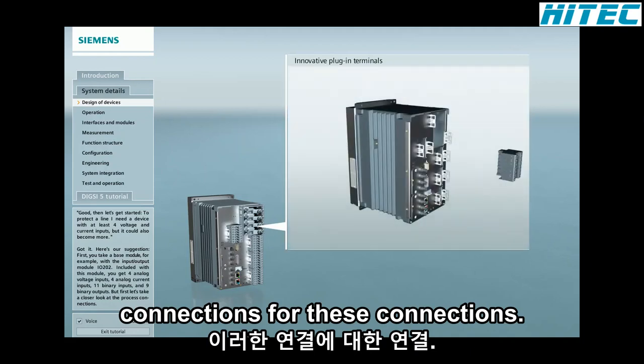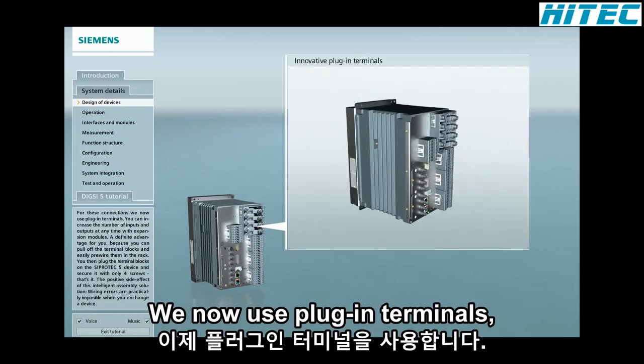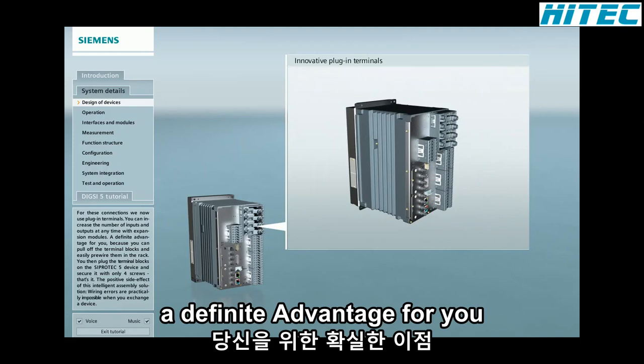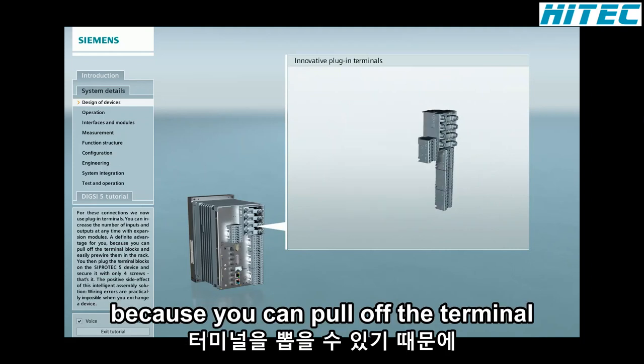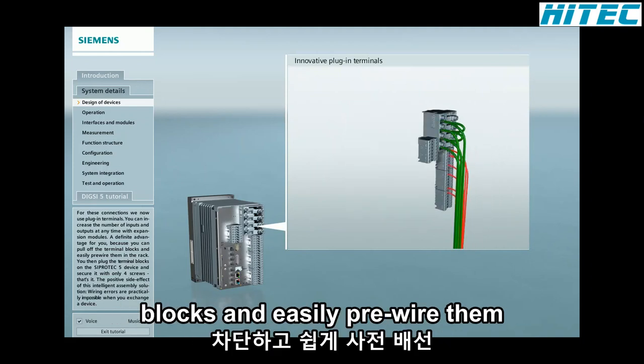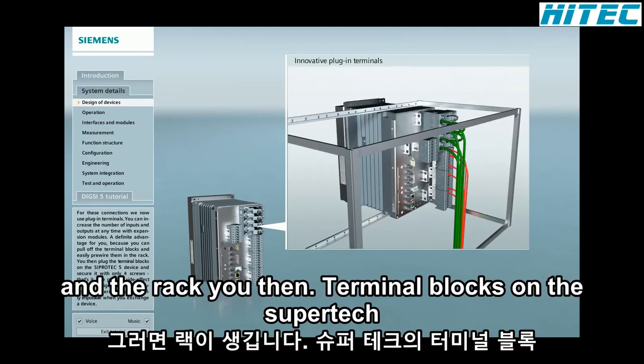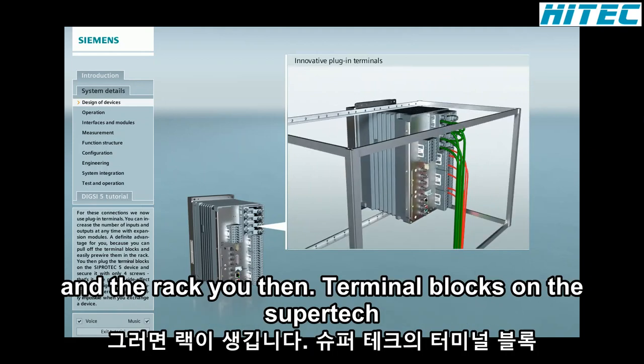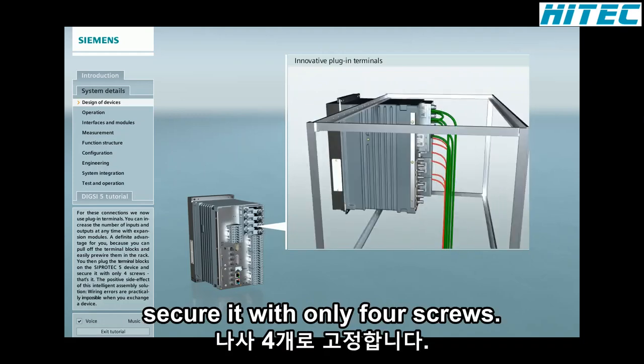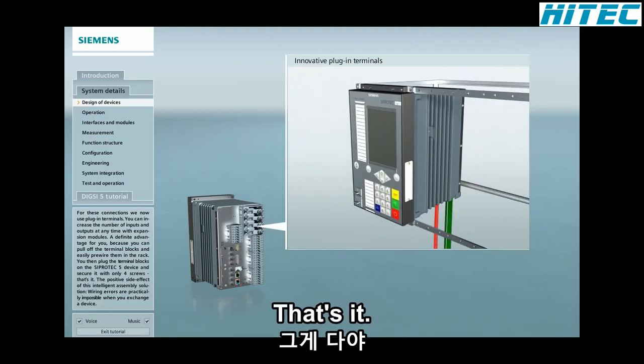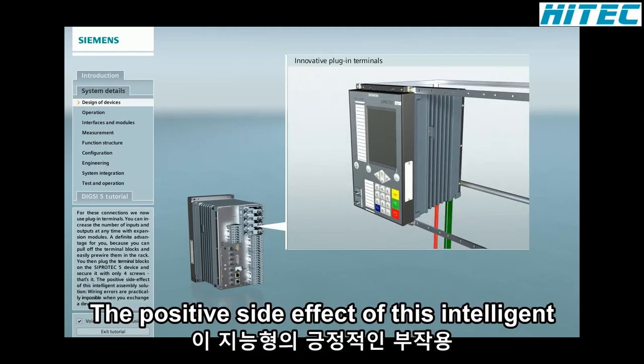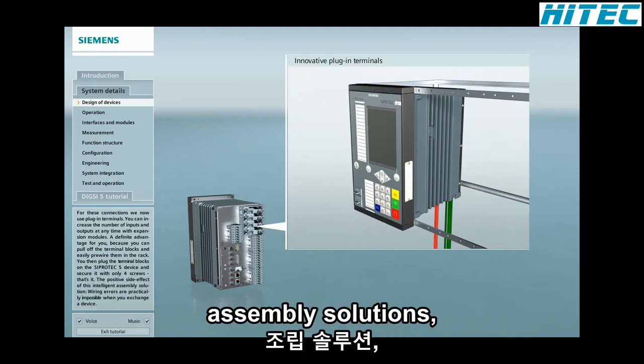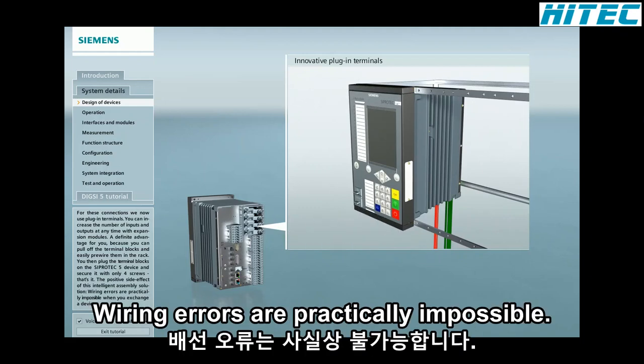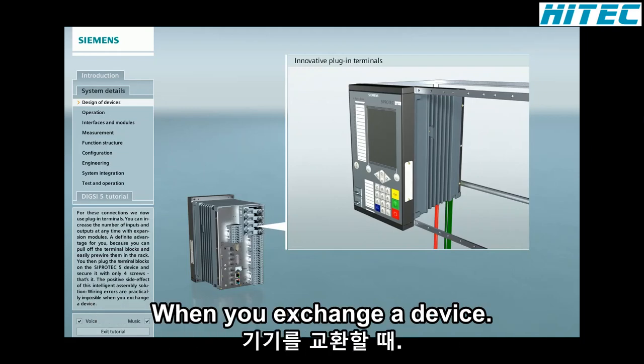For these connections, we now use plug-in terminals. A definite advantage for you because you can pull off the terminal blocks and easily pre-wire them in the rack. You then plug the terminal blocks on the SIPROTEC 5 device and secure it with only 4 screws. That's it.